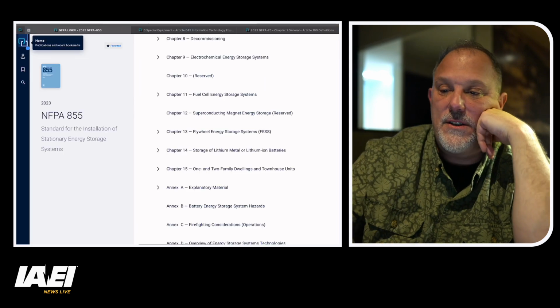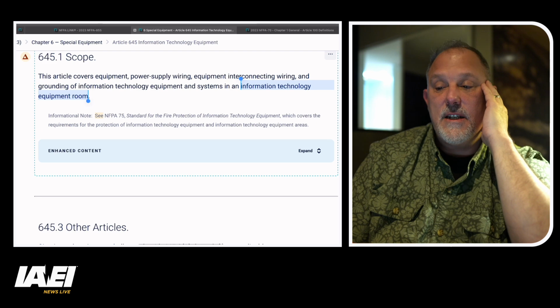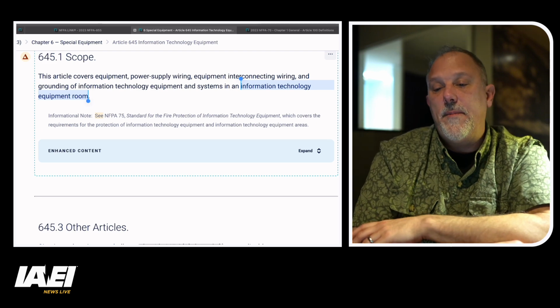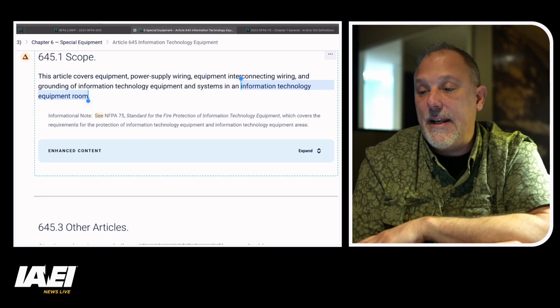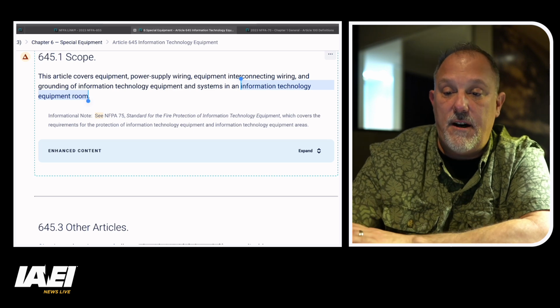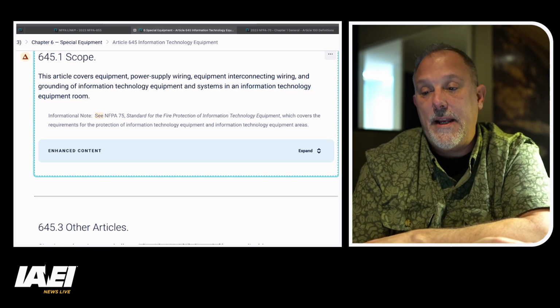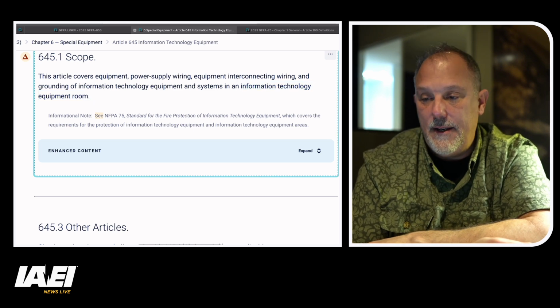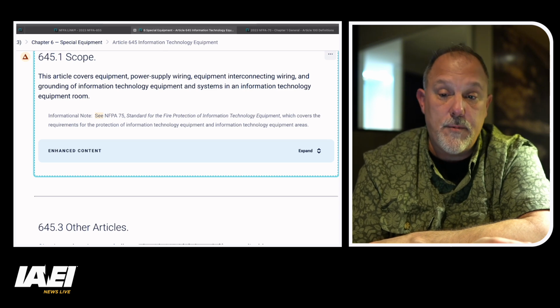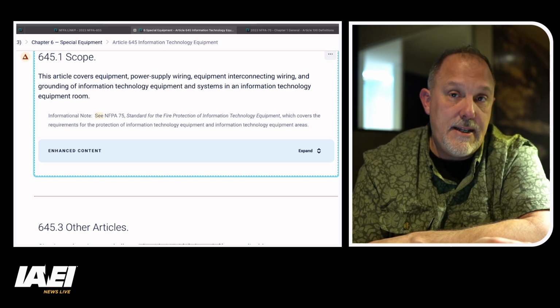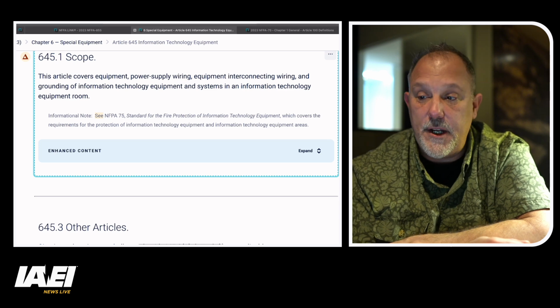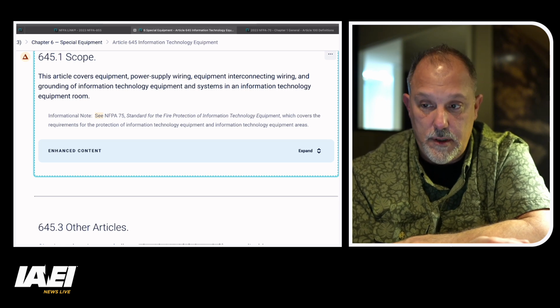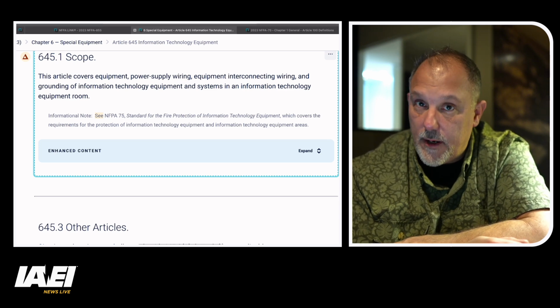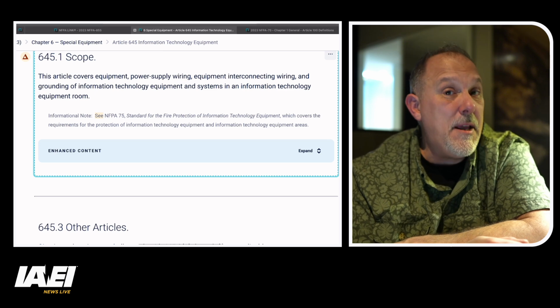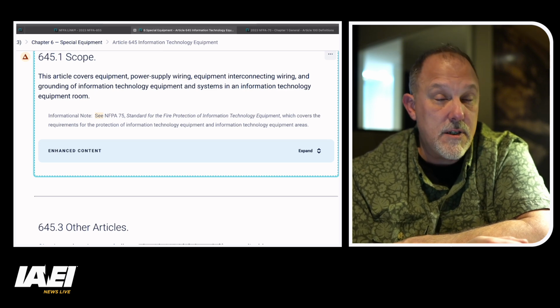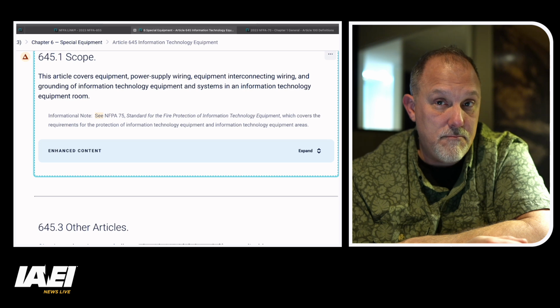So if I come back to 645, it says the article covers equipment, power supply, wiring, equipment interconnecting wiring, and grounding of information technology equipment and systems in an information technology equipment room. So if the IT equipment is not in an information technology equipment room, then this article would not apply. So maybe, just maybe, this could be our data center article.